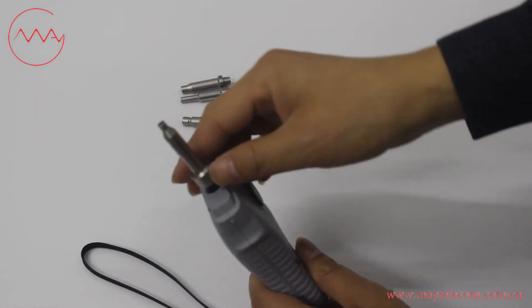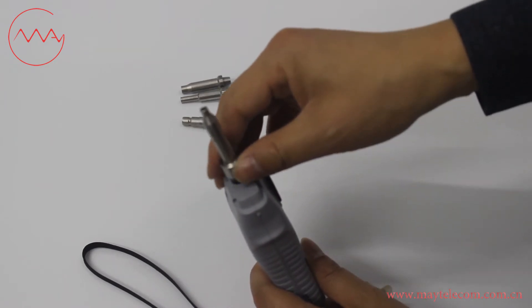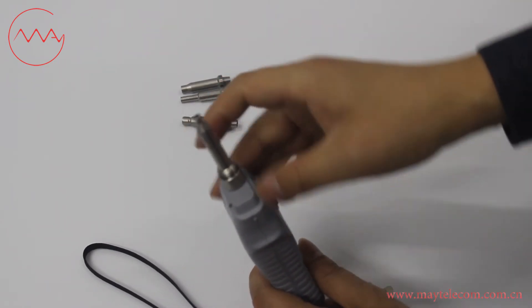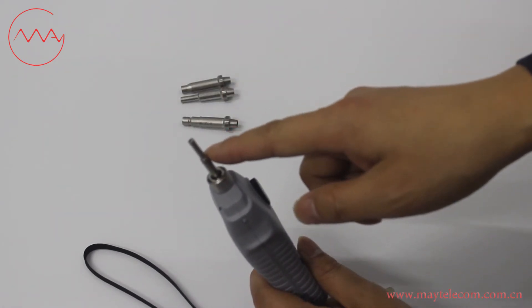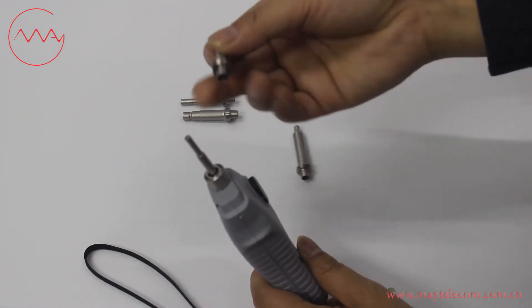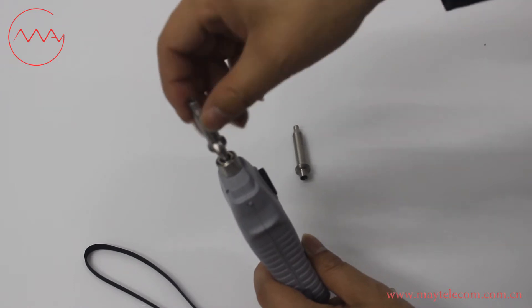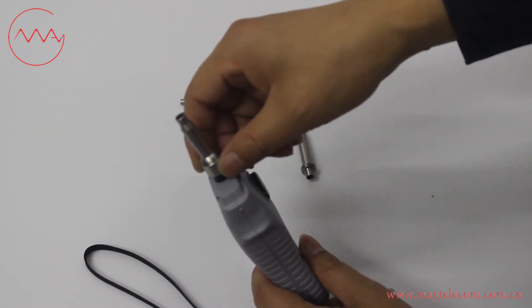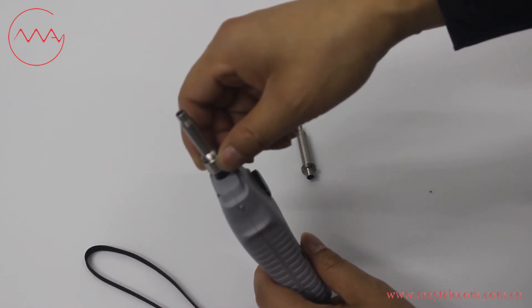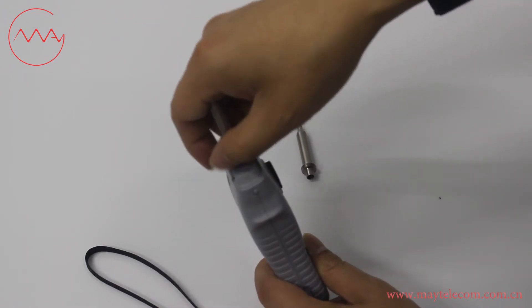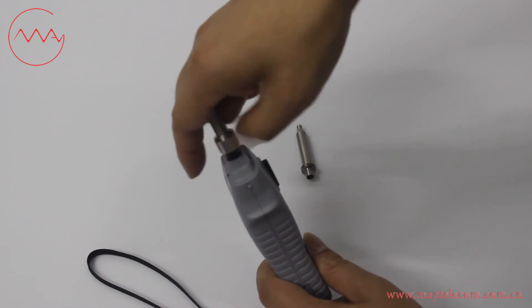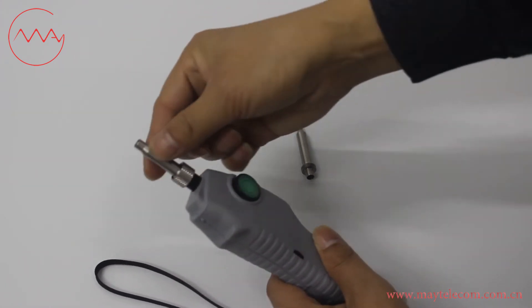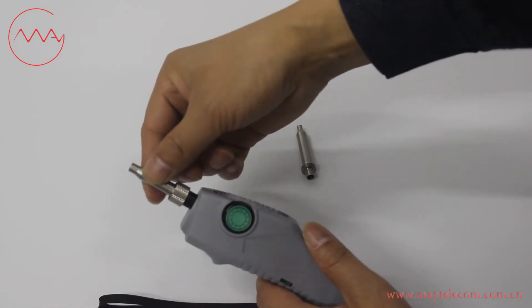Screw the assembly nut at the clockwise direction. Take out the tip. This is the length bar. Put the length bar inside the new tip. Screw the assembly nut at the anti-clockwise direction and check whether the tip is fixed.